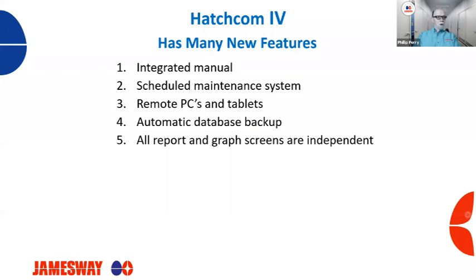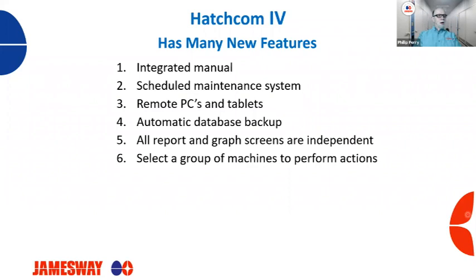It's not just one. The other is you can select a group of machines to perform actions. So you can start profiles. If you're setting three incubators at a time, you can start the profile together so you don't have to individually start the profile if they all start at the same time. You can generate reports and set up your maintenance schedule so that you can do these tasks in one operation.